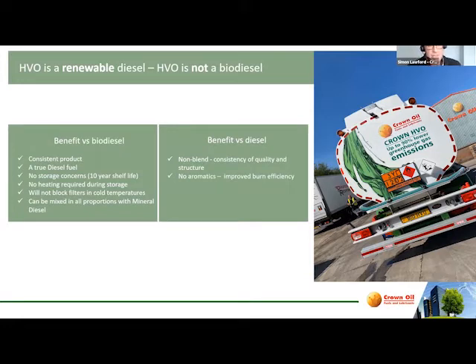There are no aromatics within HVO. This improves the burn efficiency and is in part one of the reasons why you don't get the particulate smoke that you get from standard diesel. Importantly, HVO, because of the lack of aromatics, doesn't have the health hazards associated with it as per standard fuel - i.e. carcinogenic warnings, and also the toxic to aquatic life and environment warnings that you do get with mineral diesel. Hence the health and environmental risk.